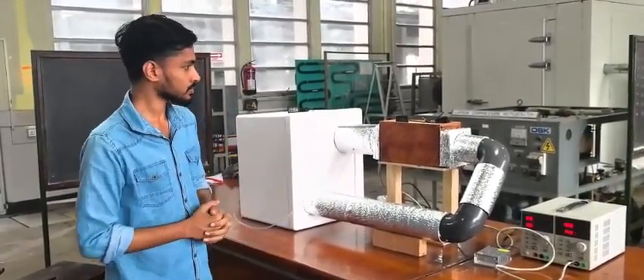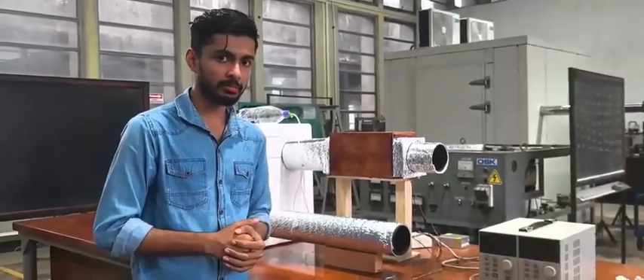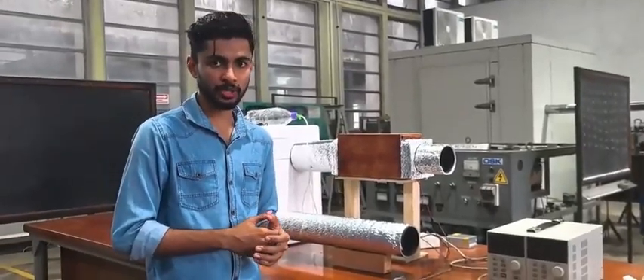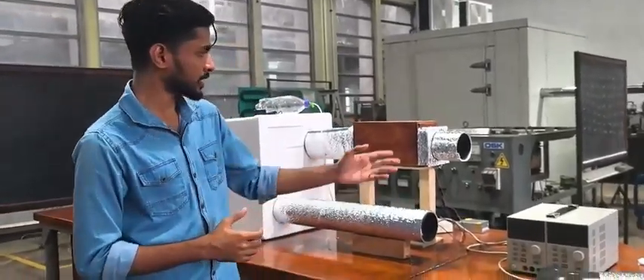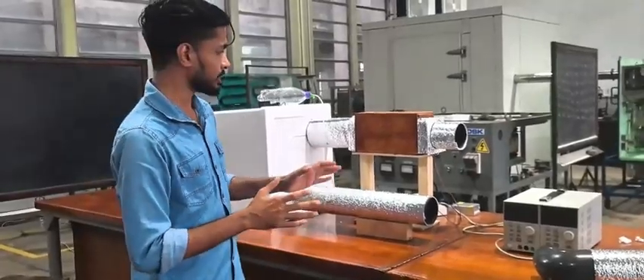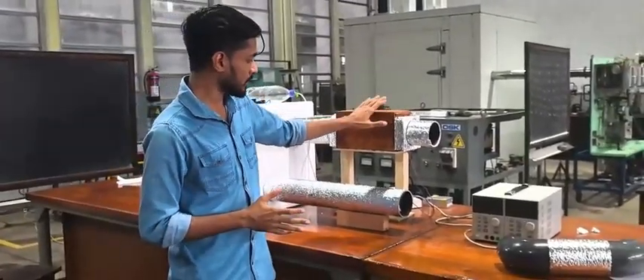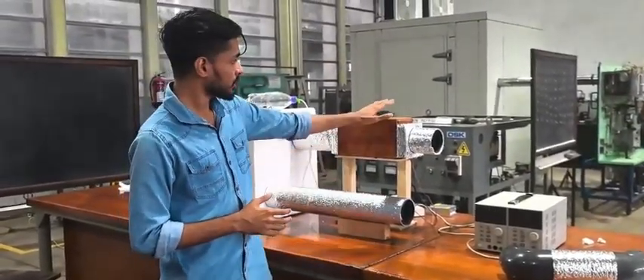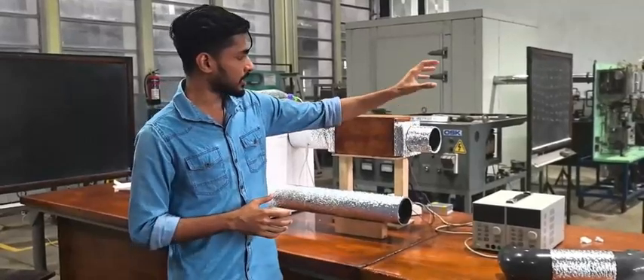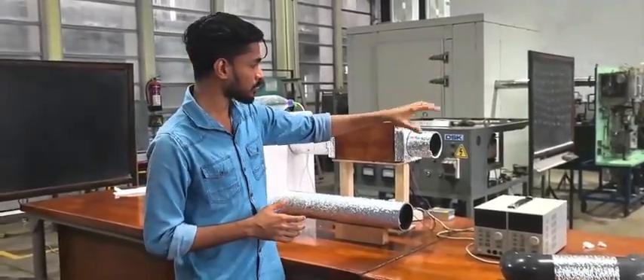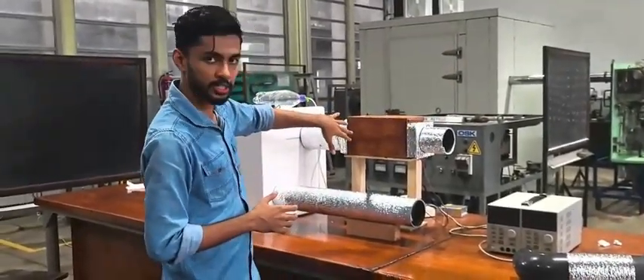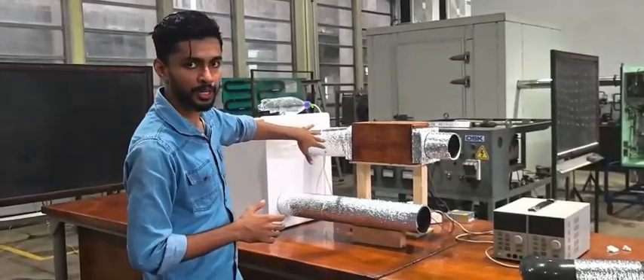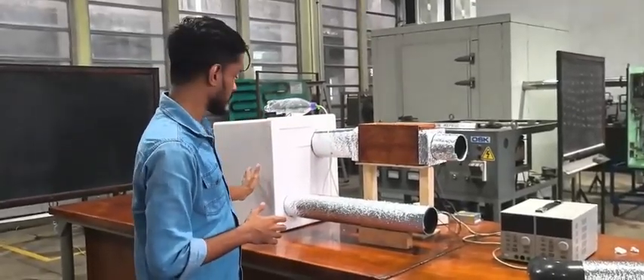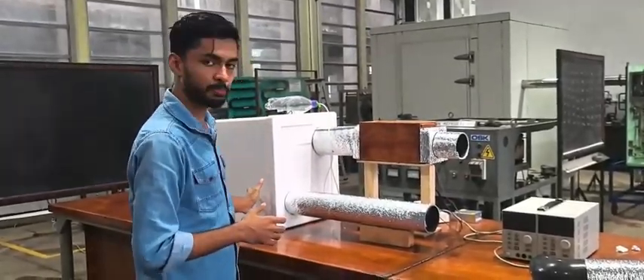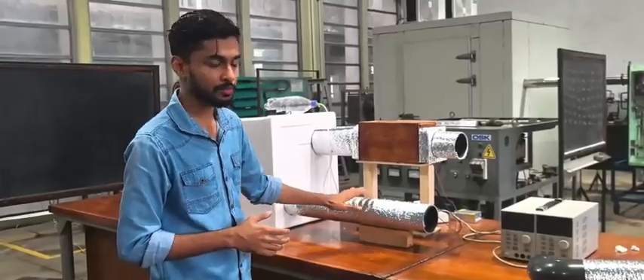There's another configuration in which we can use the cooling system, that is without the return lines in place. In this method, this is our inlet and this is our exhaust. The two fans suck the ambient air from the atmosphere, which is passed through the desiccant and then through the evaporator and then to the cool room. Then the air in the cool room is pushed out through our exhaust.